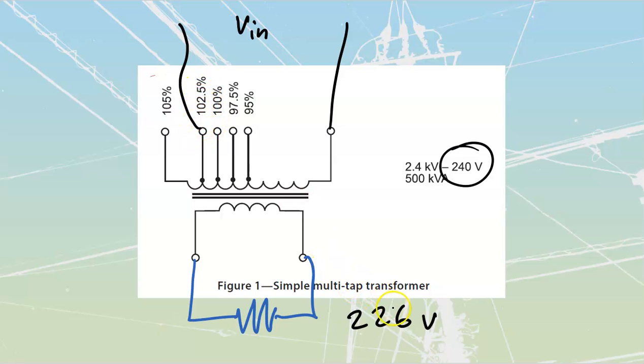which means that my turns ratio is actually 102.5% times 10, which would be 10.25. So I take my rated turns, 10 to 1. That is what this thing should be, 2400 to 240. I then multiply that 10 to 1 by 102.5%, which gets me to 10.25. What I can do now is take this 226, multiply it by 10.25, and that'll tell me exactly what I've got on the incoming side.